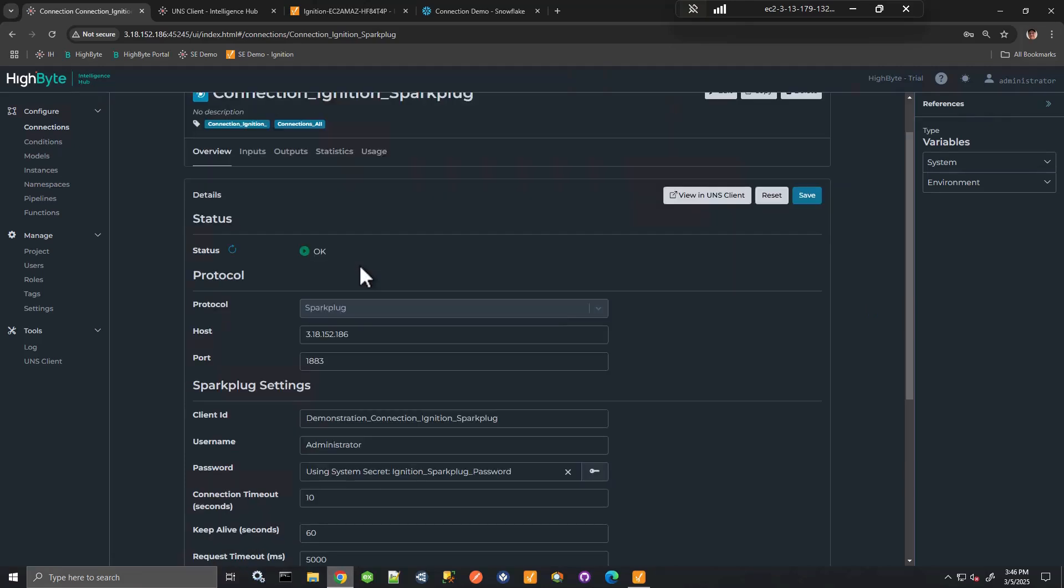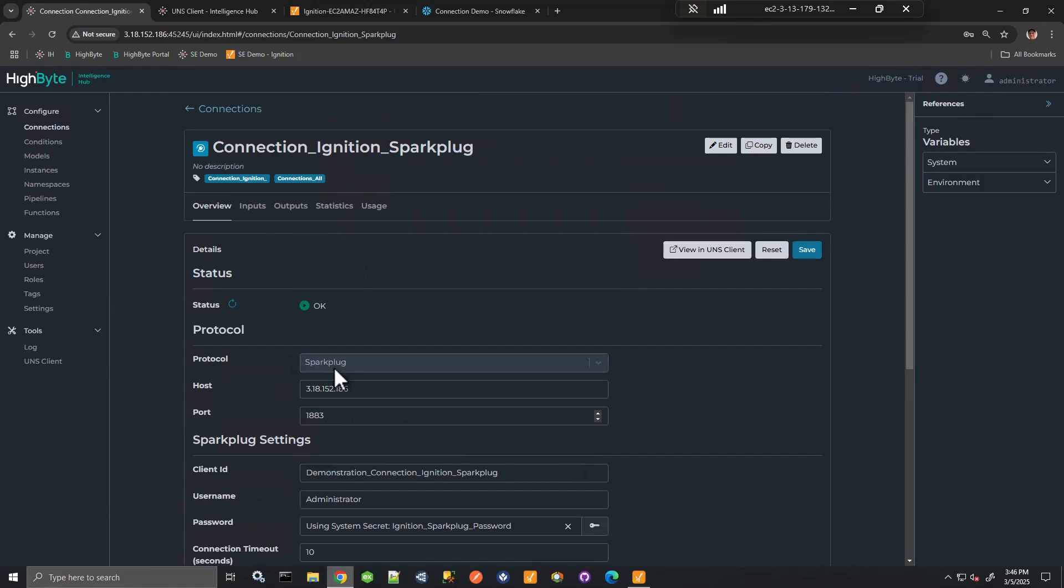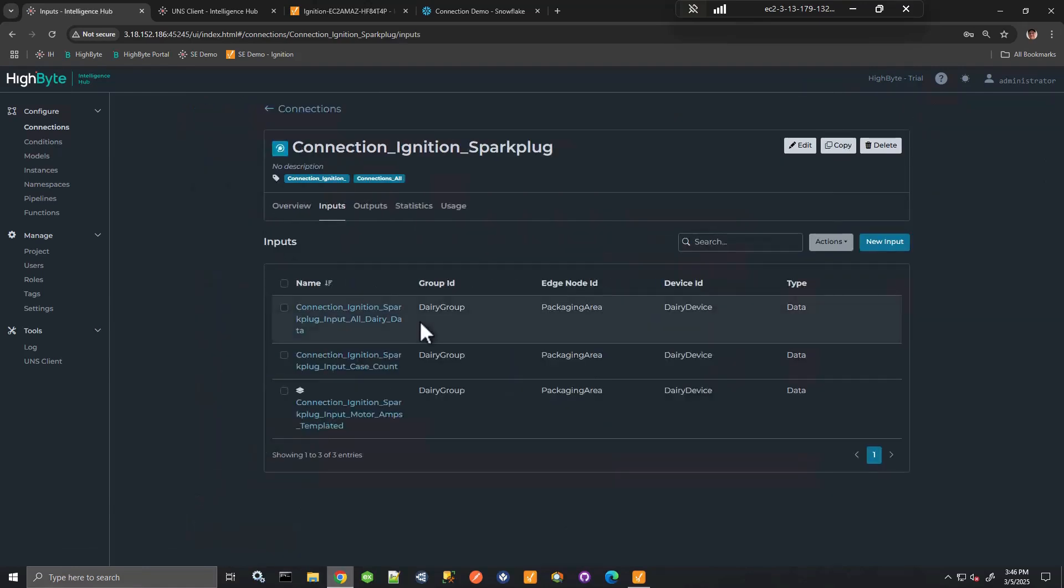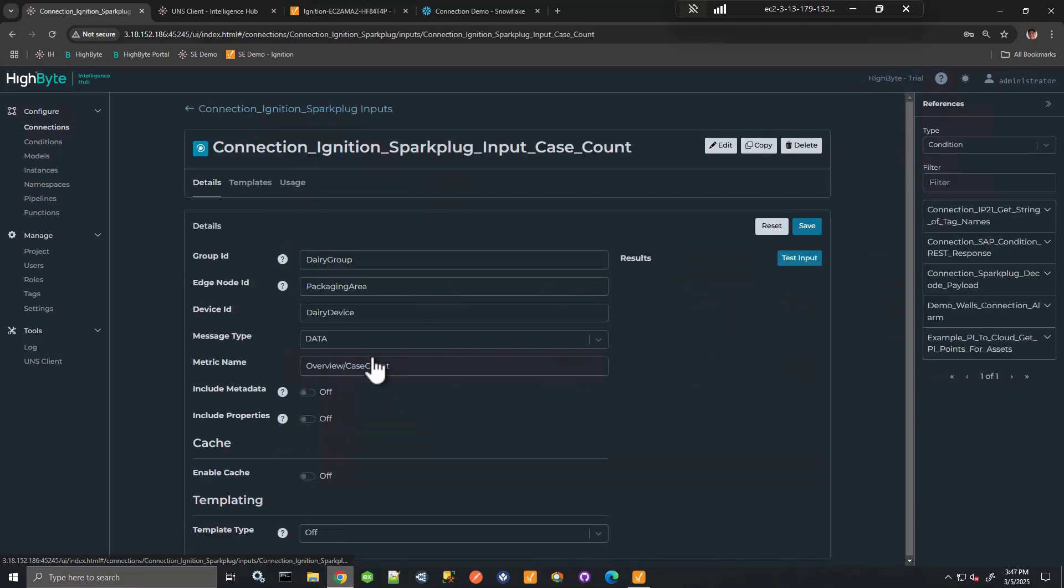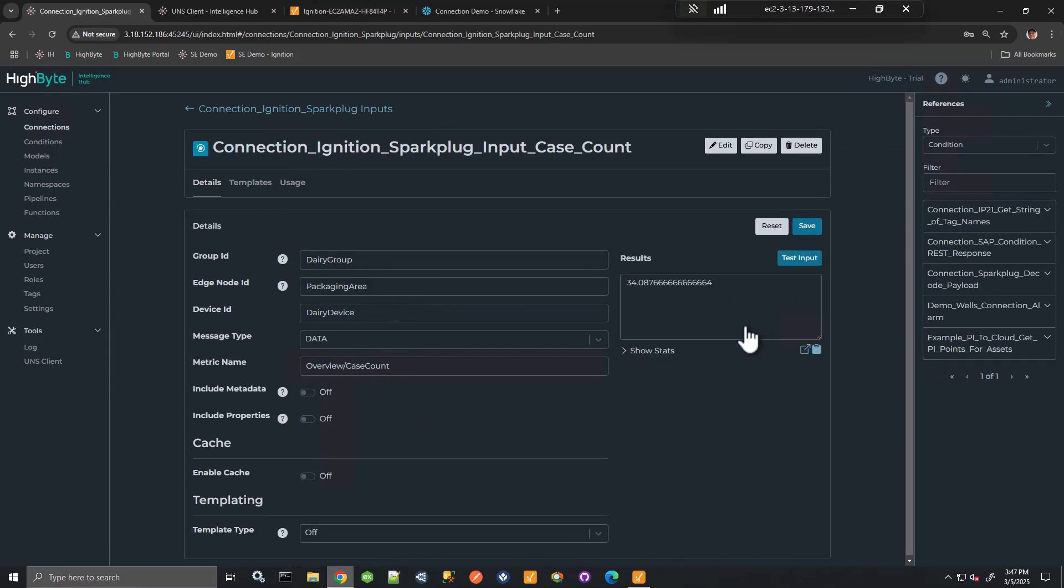So here I have a connection to Ignition. Host is identified. The port is identified. And what I can do is I can create connection inputs. And that might be simply defining the edge node device ID and obtaining data for a specific metric, like in this case the case count in the dairy simulation in Ignition.